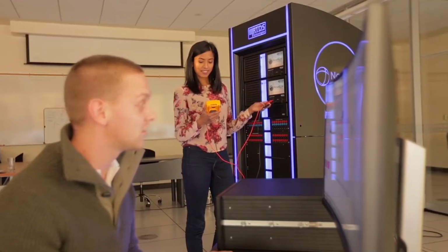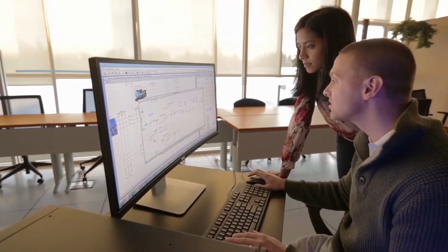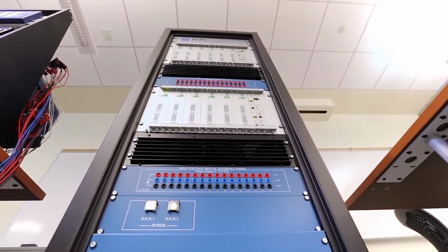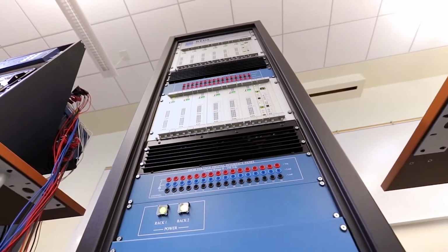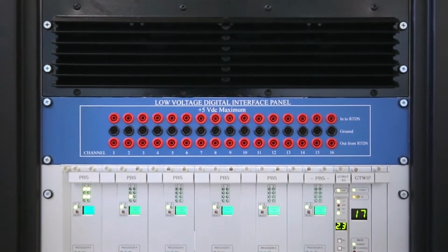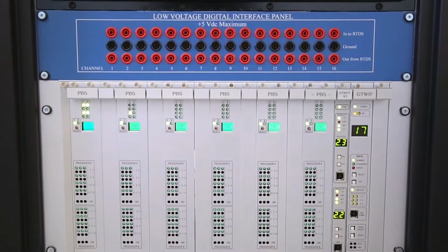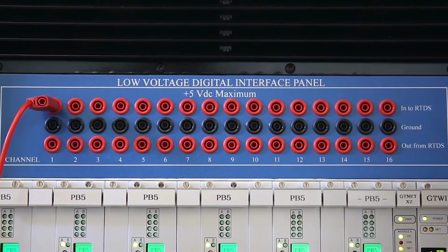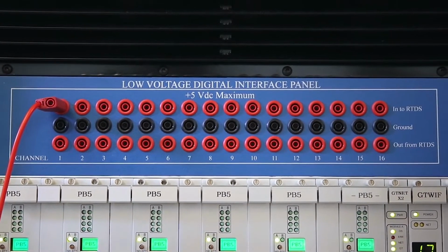The simulation time step determines both the sampling period of the power system data and the amount of time available for the calculations required to reach the simulation output. Though the average simulation time step is between 25 and 50 microseconds, time steps in the hundreds of nanoseconds range may be required to simulate the switching of power electronic converters.